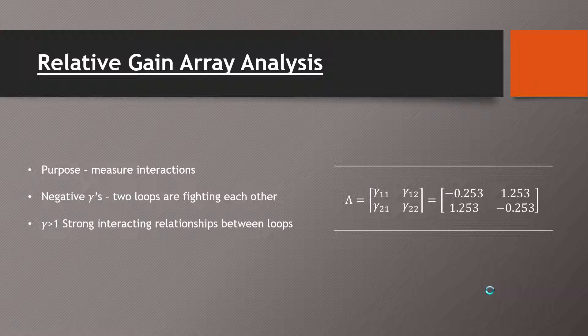As shown, you can see that there are two negative gammas, and these show that our two loops are fighting each other as they're trying to reach their individual set points. And we also had two gammas that were greater than one, which showed that we had strong interacting relationships between the two loops that we were trying to control.